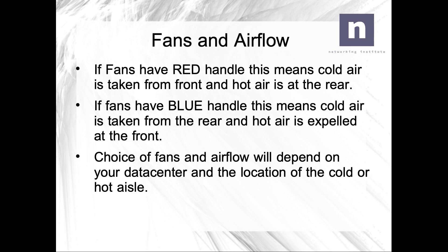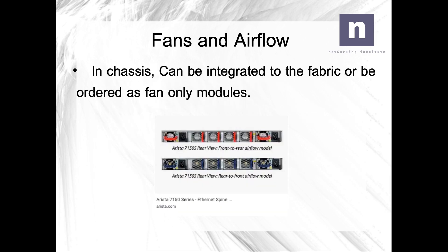If the fans have a blue handle, cold air is taken from the rear and hot air is expelled from the front. The choice of fans and airflow will depend on your data center environment and the location of your hot or cold aisle. In the chassis, fans can be integrated to the fabric card or ordered as fan-only modules.